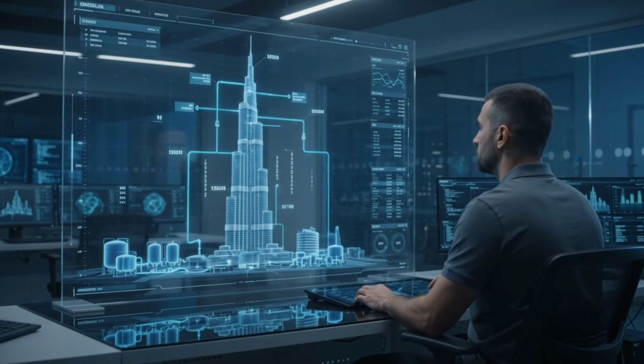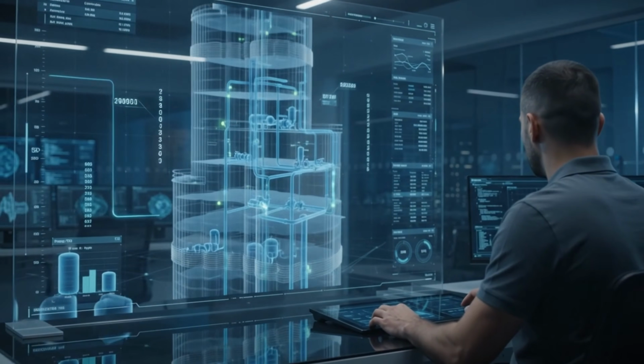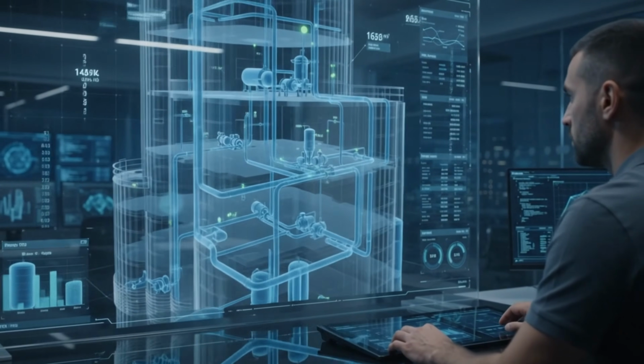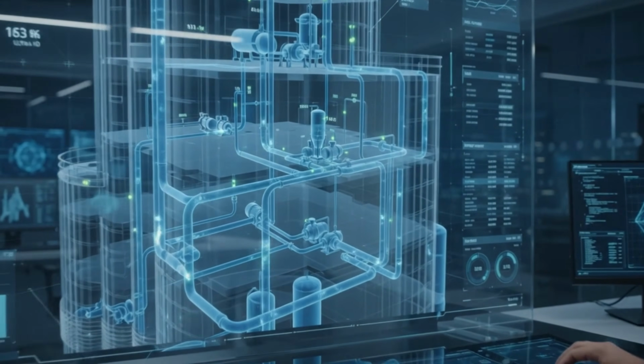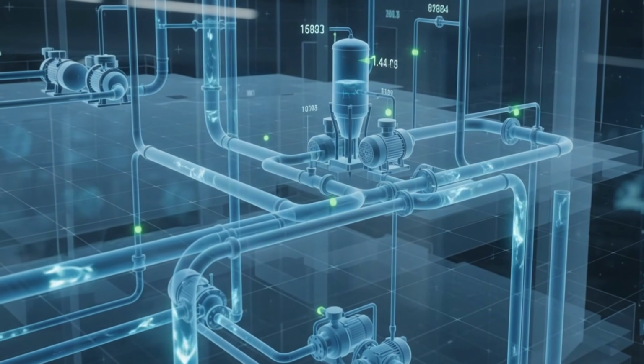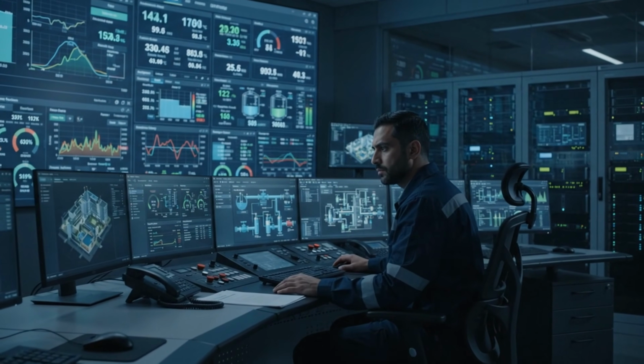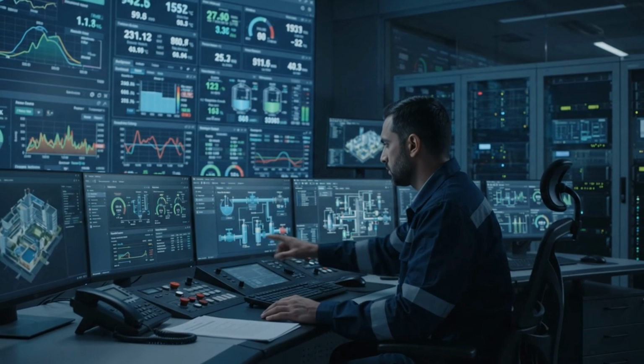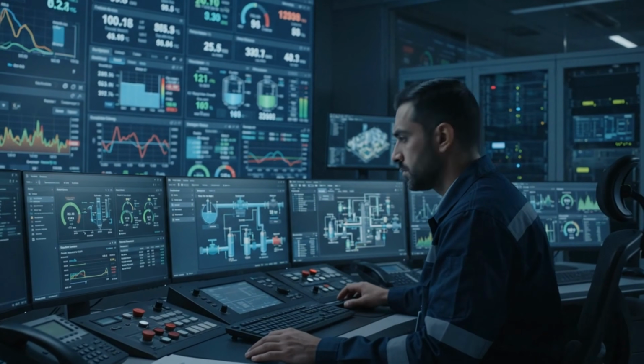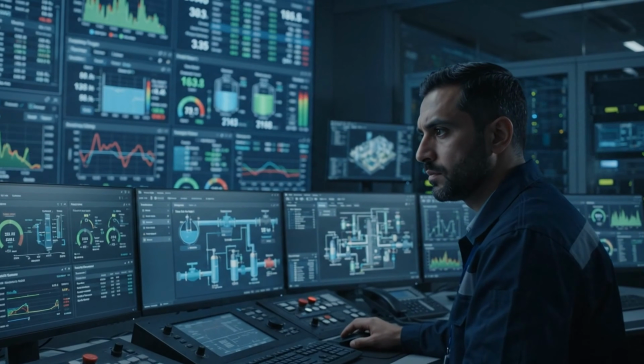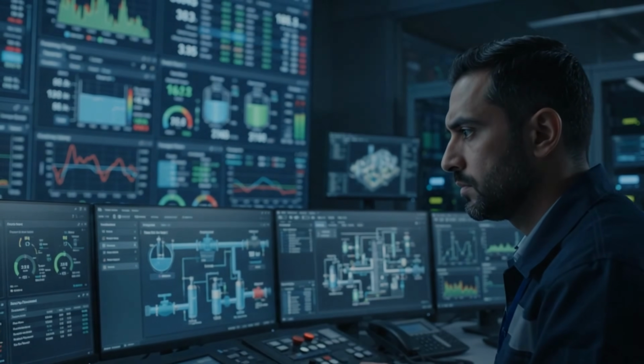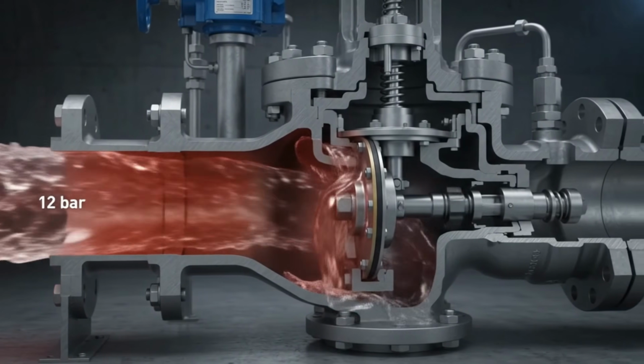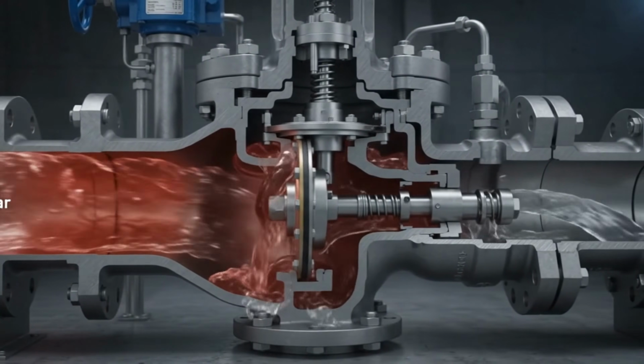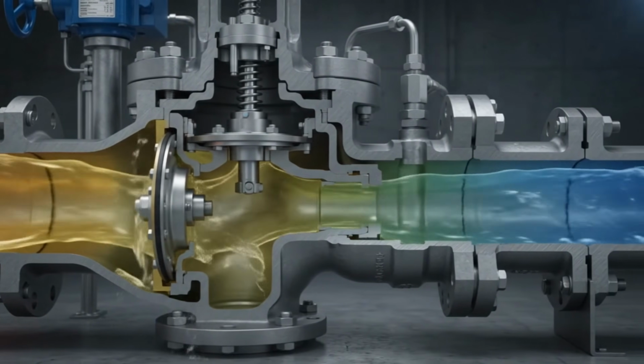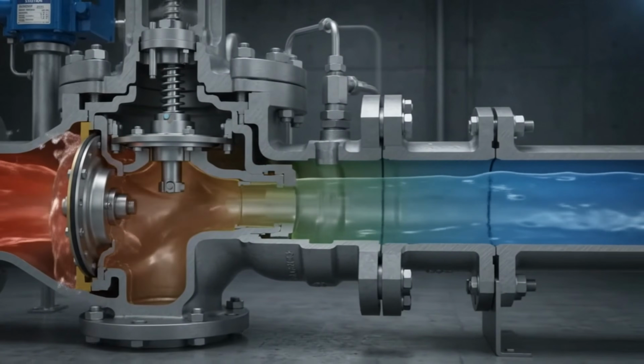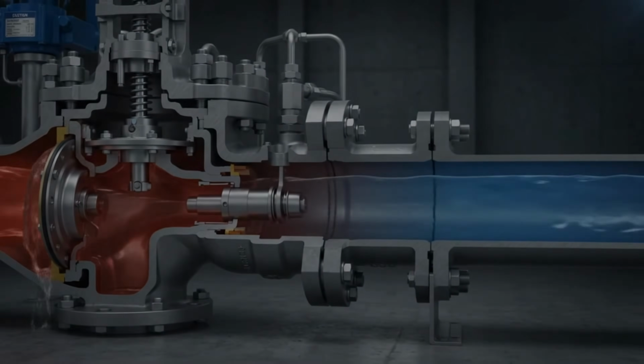Engineers now maintain a complete digital twin of the Burj Khalifa's water infrastructure. This perfect replica receives real-time data, allowing changes to be tested virtually. From this control room, a small team of engineers monitors every valve and every flow meter in real time, the nerve center of a water system serving an entire vertical city. A single pressure-reducing valve performs an invisible miracle thousands of times every day. The pressure a human hand expects when turning a tap.